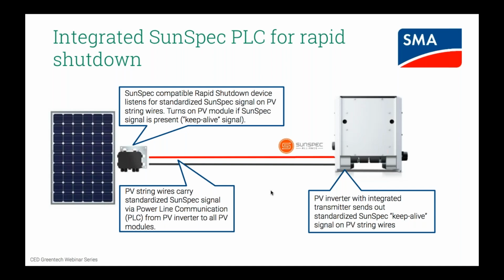And then within the array, you have module level devices, like shown on the left here, that are essentially listening for that keep alive signal. If the inverter is up and running and it's sending that signal, then the devices receive that signal and they allow the energy from the modules and the array to flow through to the inverter. But if the PV system is shut down, in the case of, for instance, an emergency response, the inverter's powered down, and they stop sending out that signal. Now the module level device is not receiving that signal, and they basically disconnect the modules each from the string so that you de-energize the array to the levels required by NEC.